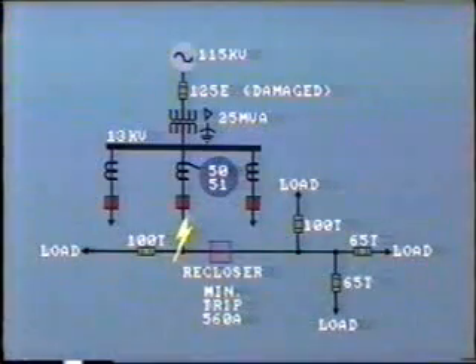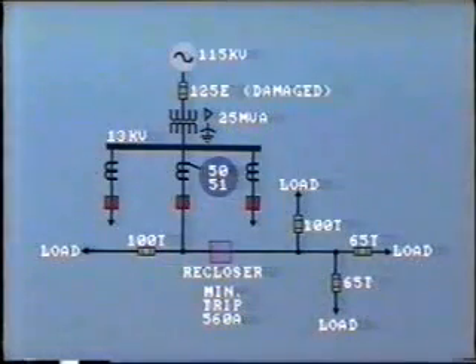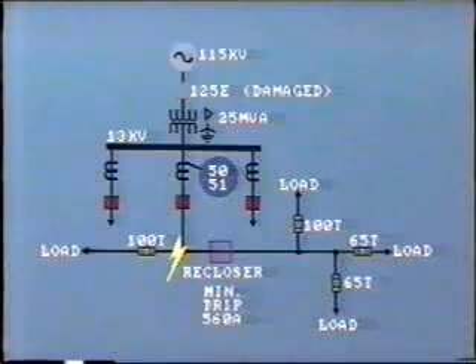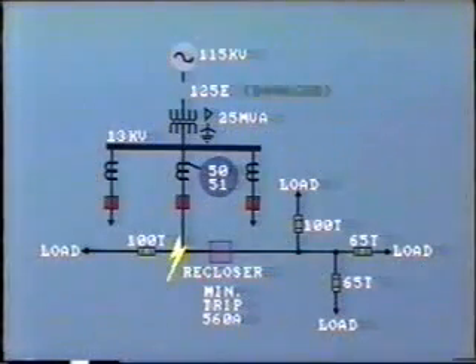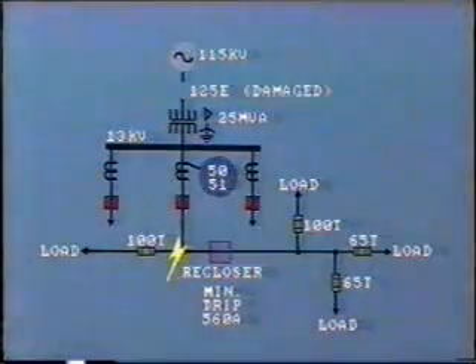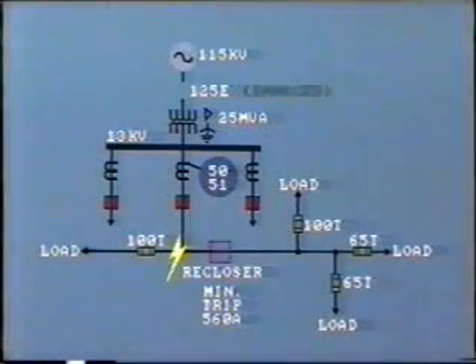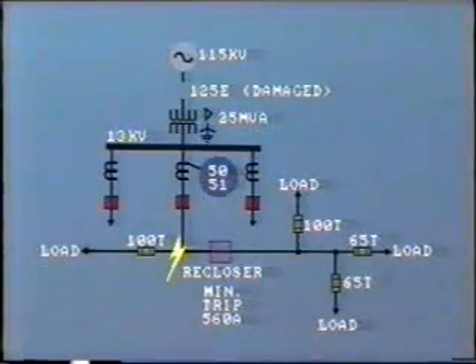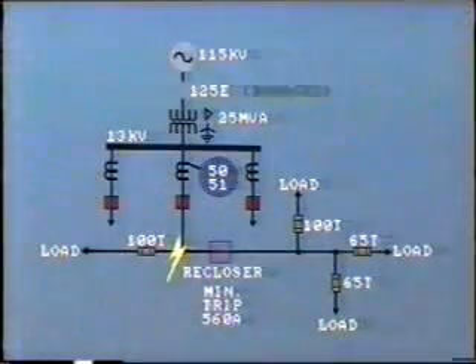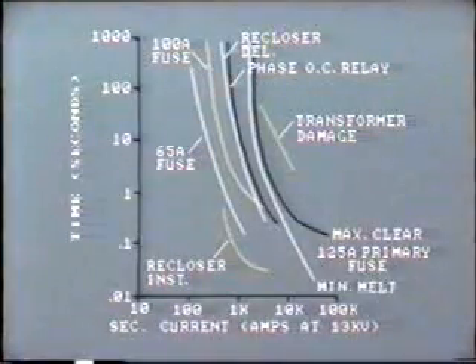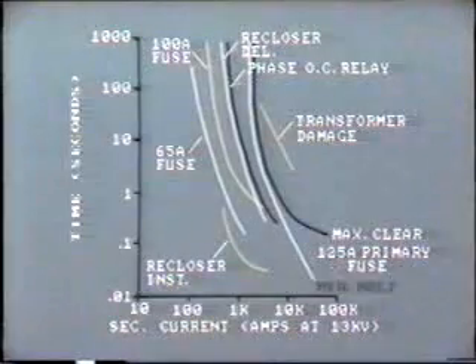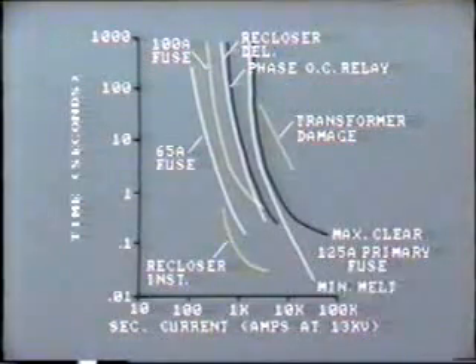Before the fuse element melts open, the breaker may eventually open and clear the fault. So now we have a damaged fuse that next time round will probably blow in a very short period of time, long before operation of any of the downstream protection devices. This will isolate many more customers than necessary. In checking coordination circuits, we must always use the pre-melt curve. For now, switch off the tape and review this material in your workbook.